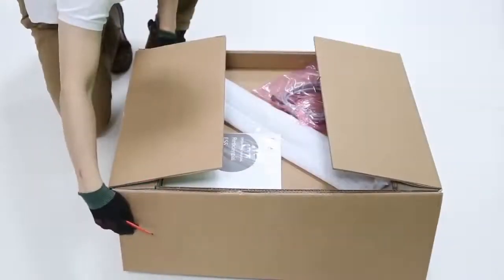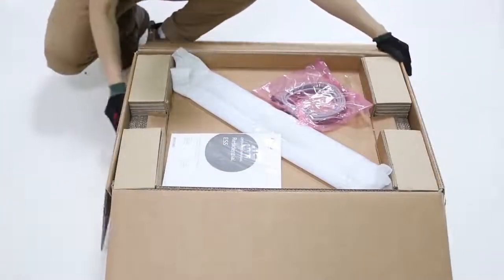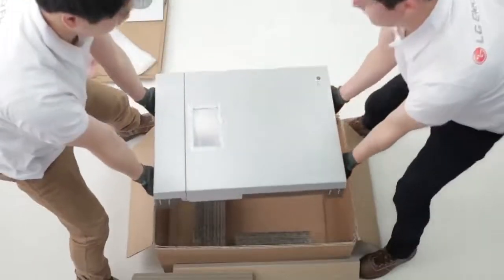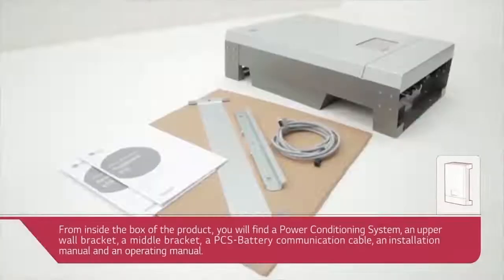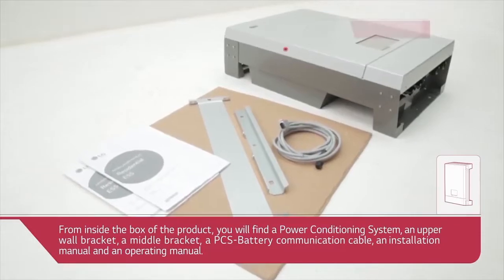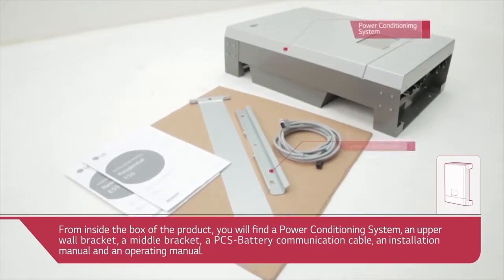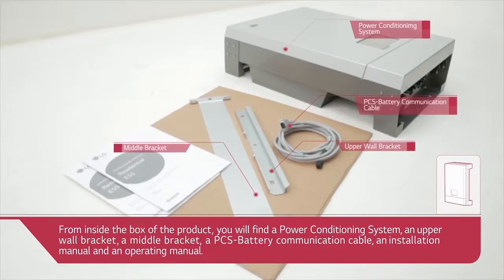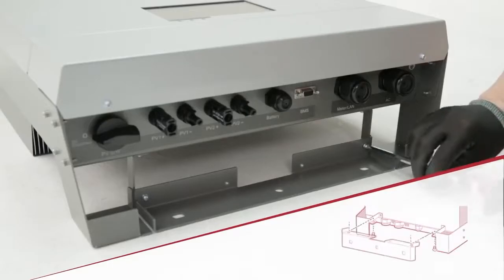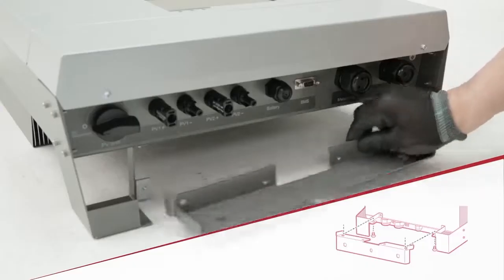Now let's have a look at the process of installing the power conditioning system. First, open the box of the LG PCS and lay the PCS flat on the floor with the front side facing up. From inside the box of the product, you will find a power conditioning system, an upper wall bracket, a middle bracket, a PCS battery communication cable, an installation manual, and an operating manual. The lower wall bracket is attached to the PCS as part of the product. Disassemble the lower wall bracket from the PCS.